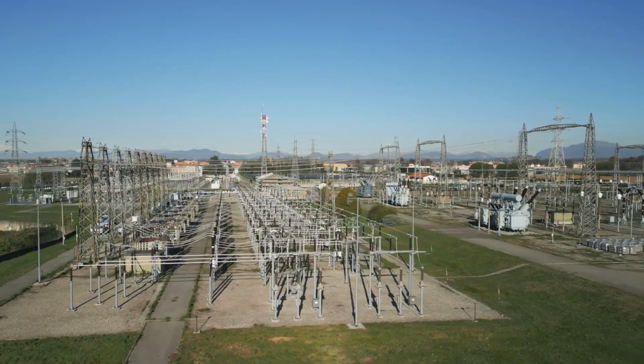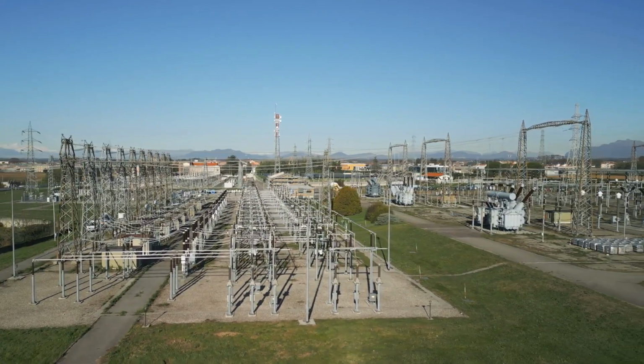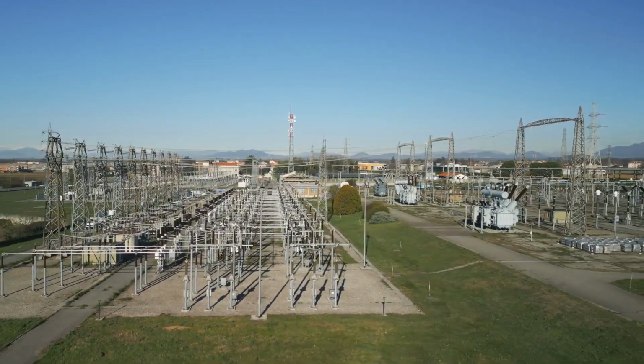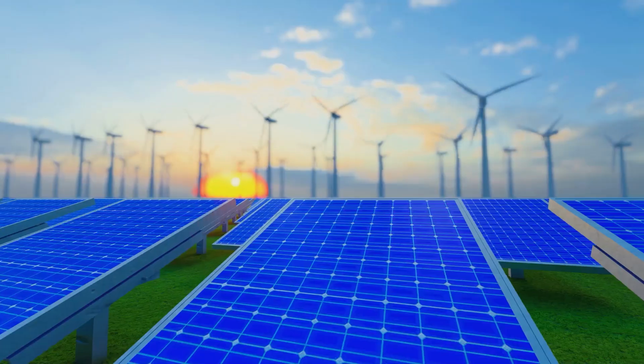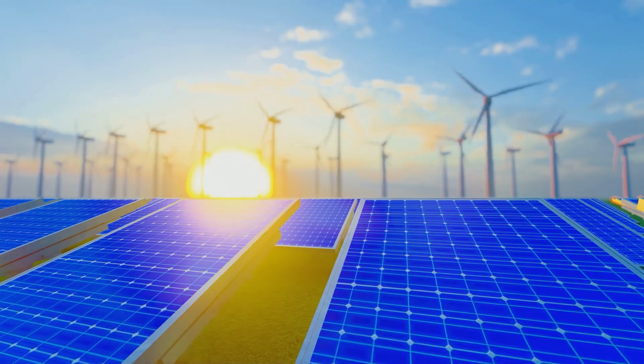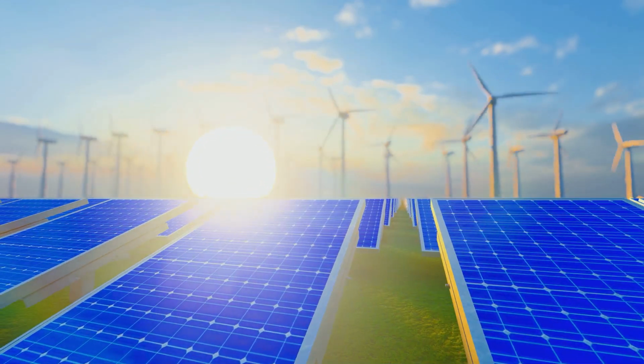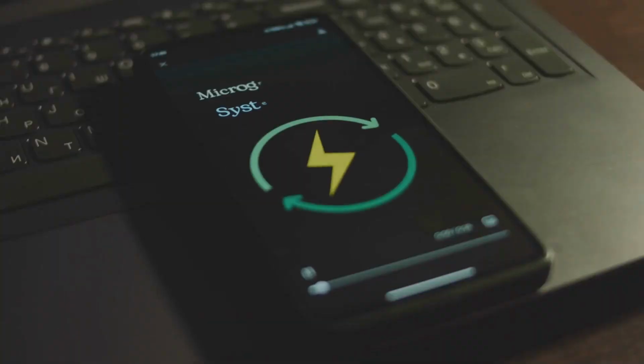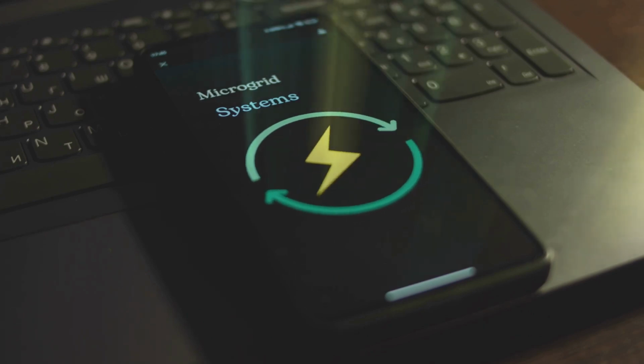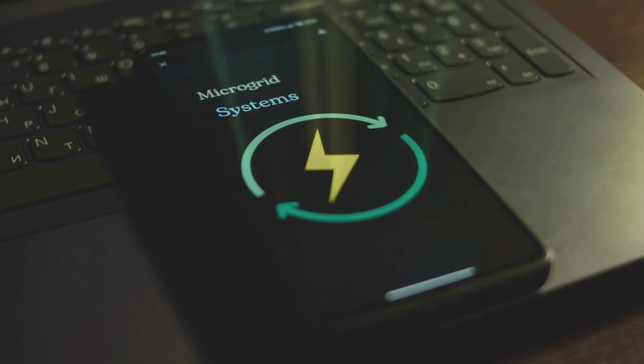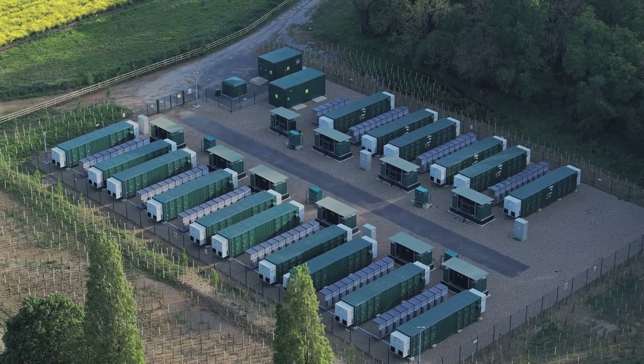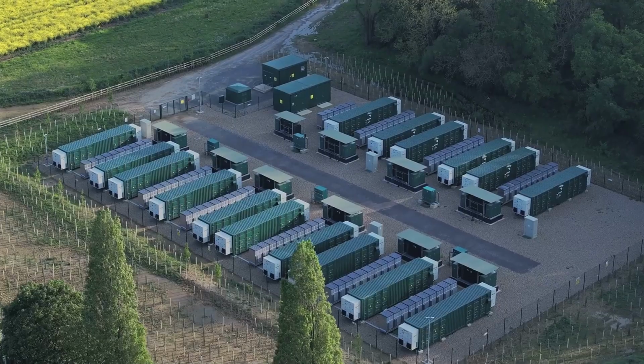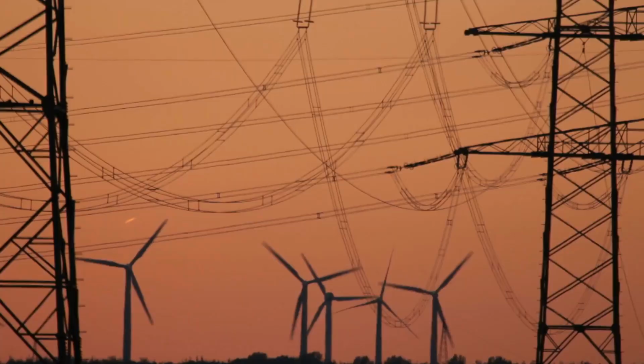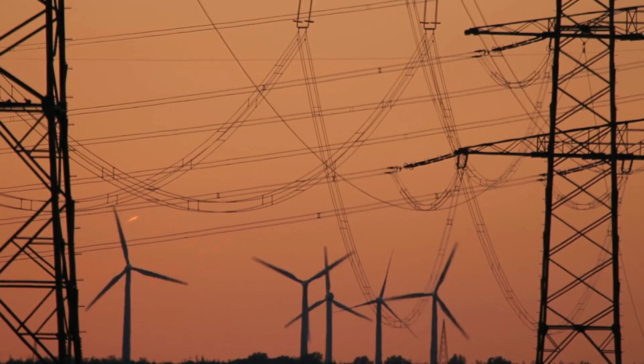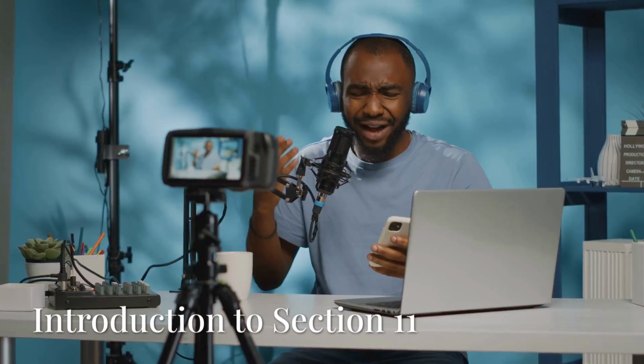Sections 9 and 10 ensure that DERs not only survive faults, but cooperate and communicate as part of an intelligent system. No matter what type of device you're deploying, it must meet the same grid-facing FRT criteria. Every DER must be able to share its behavior, receive updates, and provide diagnostics. Aggregated and modular systems must act in harmony, not chaos, during grid events. This is what turns DERs into grid allies, not just generators.